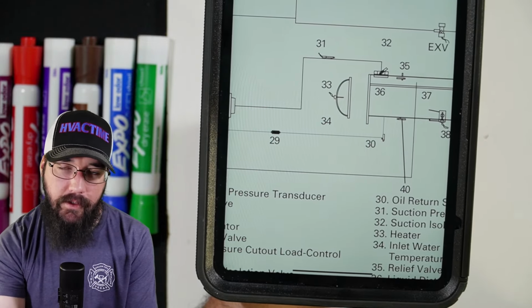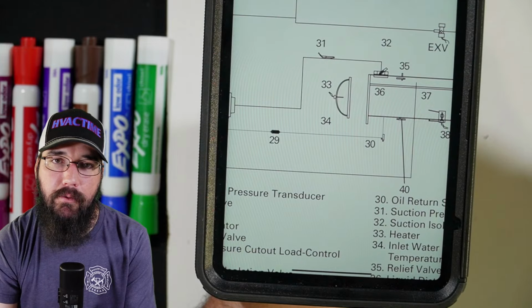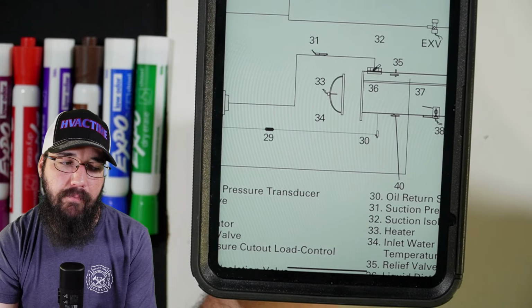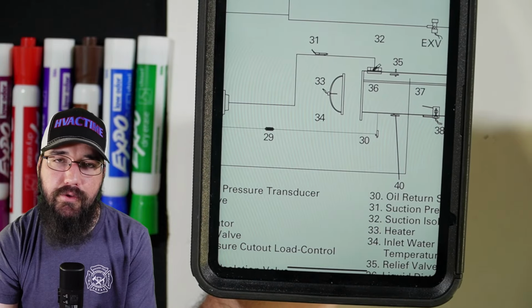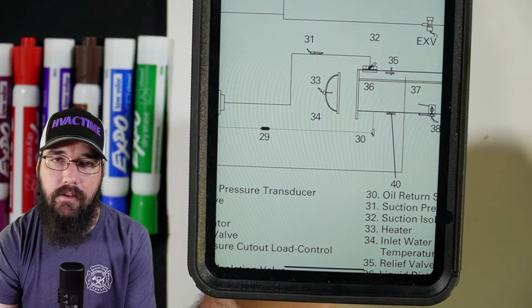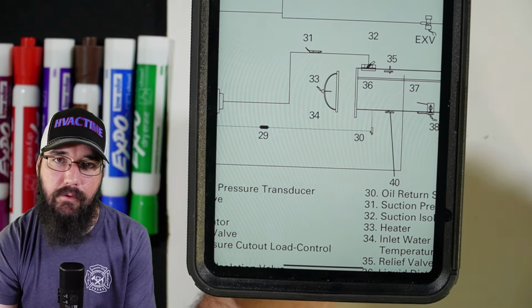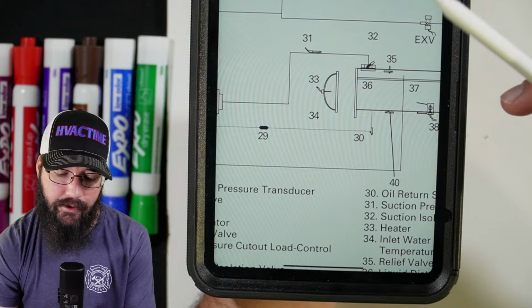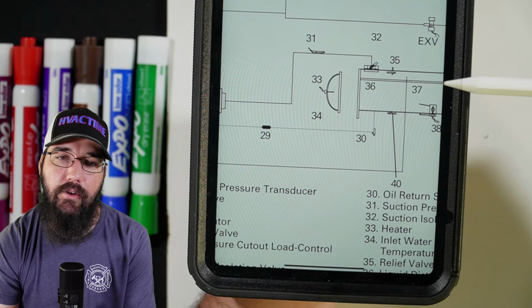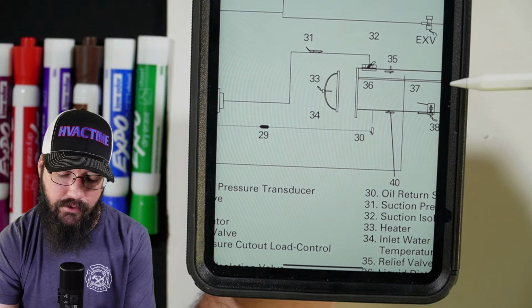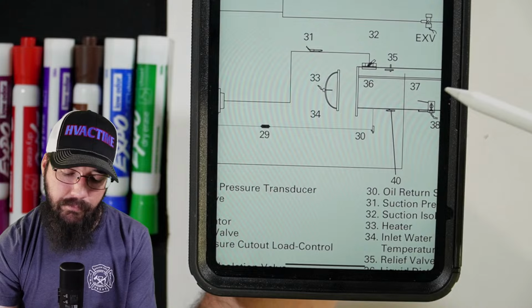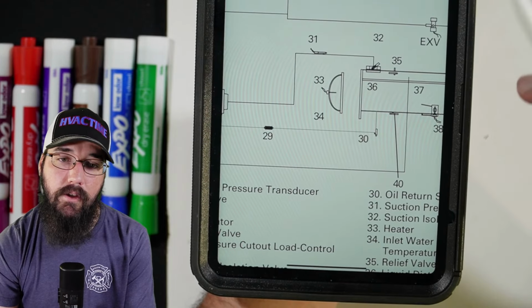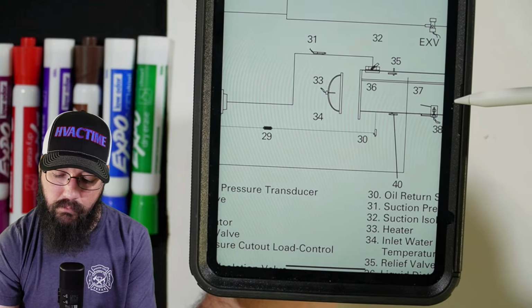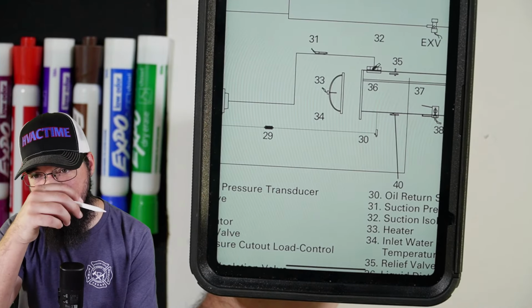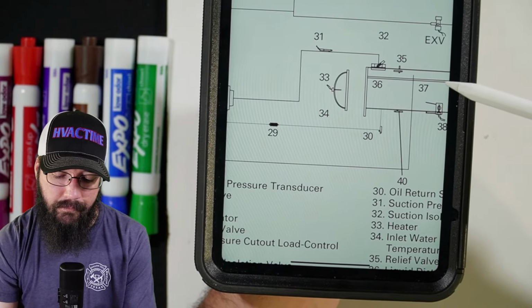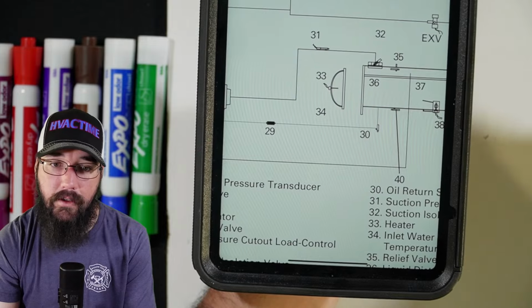Let's see. One of the ways to know is just pay attention to your approach value. So if your approach is really high, but you're confident you have proper liquid refrigerant charge and your tubes and flow, like your heat exchanger, is working correctly, but yet you still have high approach values, which on this machine should be like, what, 3 degrees. So approach is the difference between saturation and leaving water temperature. If it gets to say 3 or 4 degrees or above that at load, that's when we start having to ask questions, and it could be an oil issue.